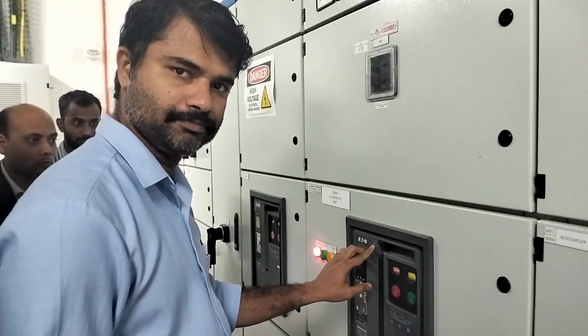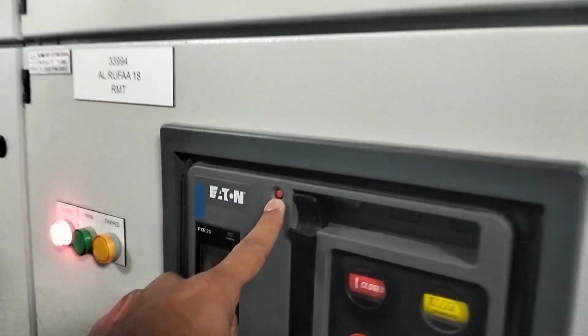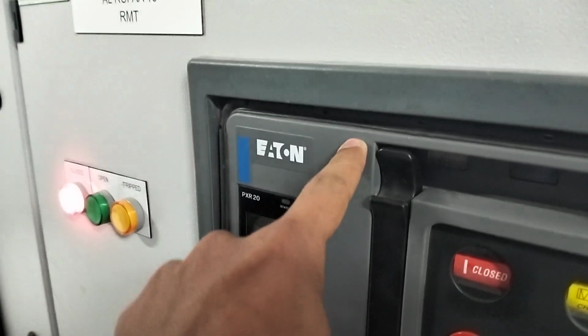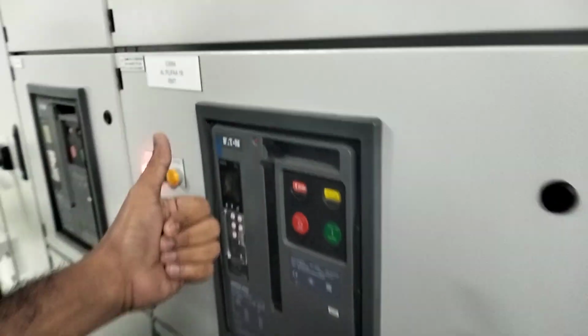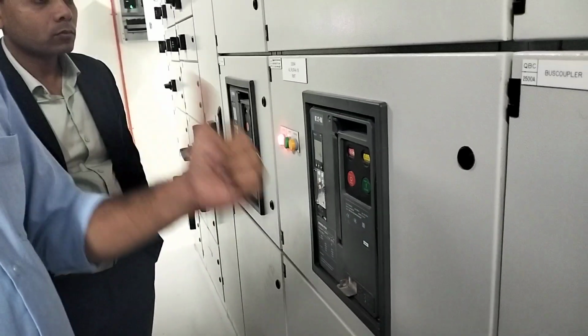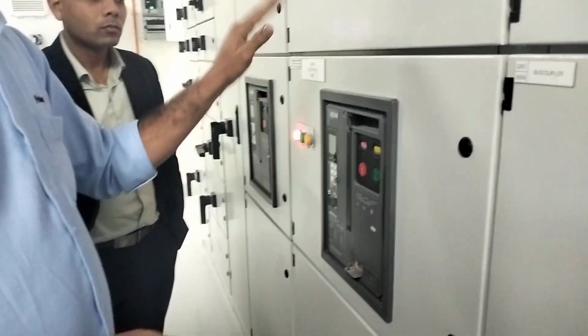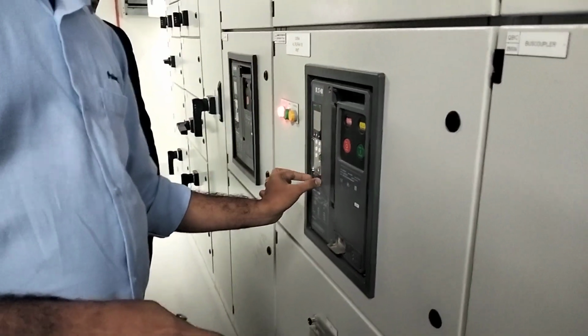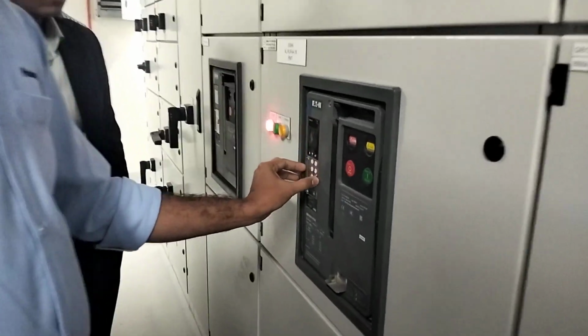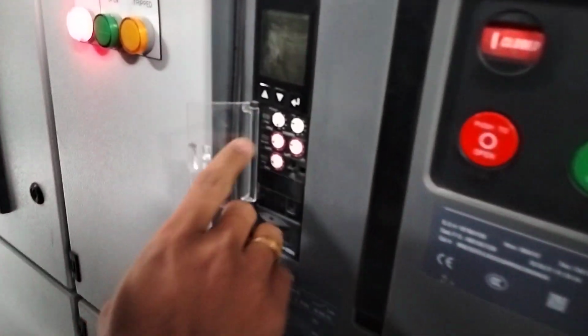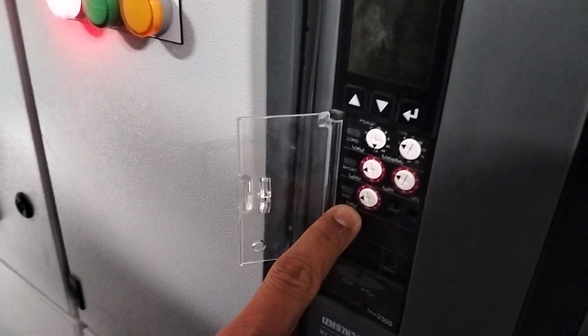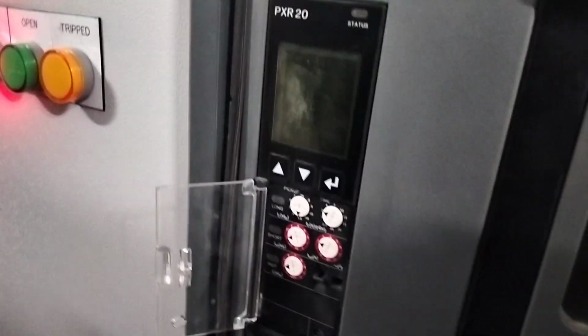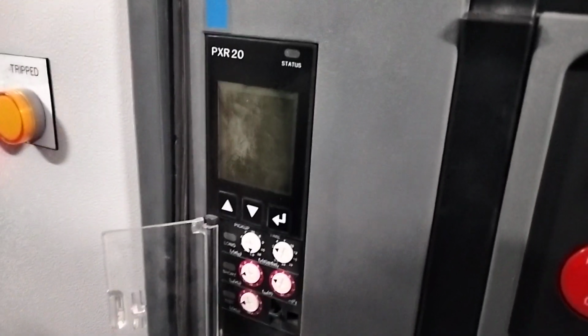Look at the ACB knob. All the ACBs have a mechanical reset, and it should be inside. If it is outside, it means some short circuit or overload has happened in the breaker. This is the electronic trip unit. We can see the long time, short time, and instantaneous trip units, LSI protection. This is a microprocessor-based trip unit.